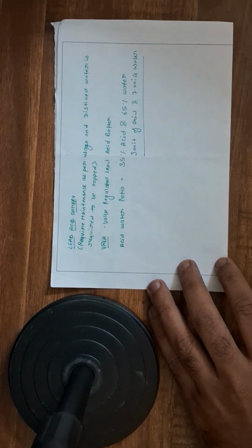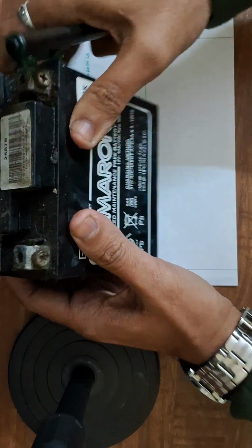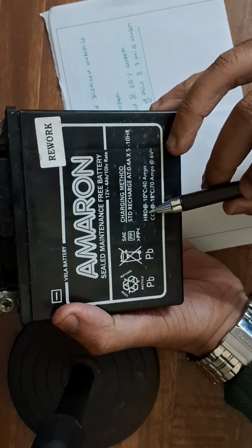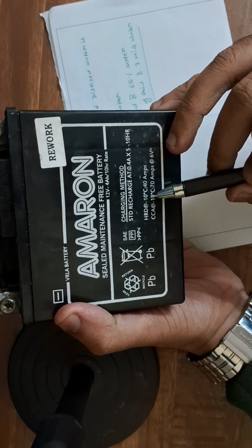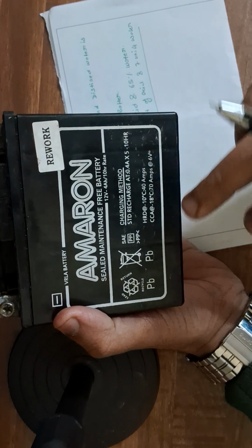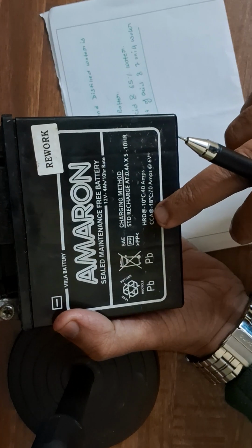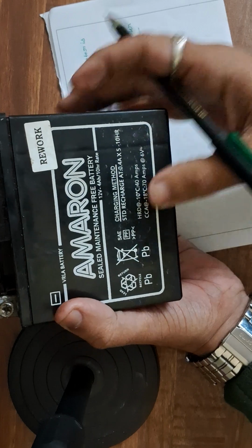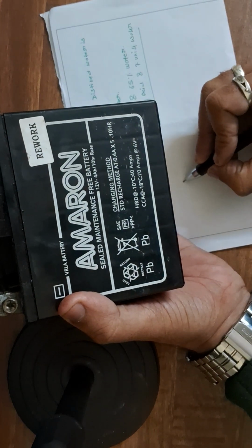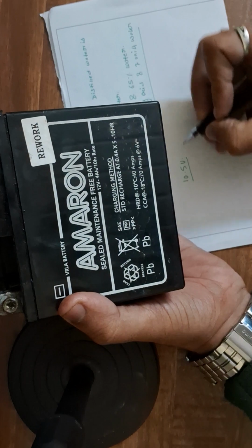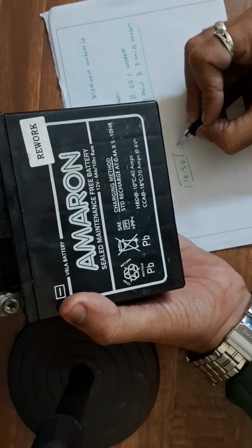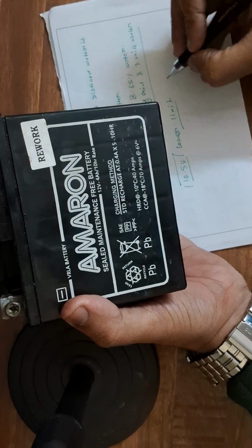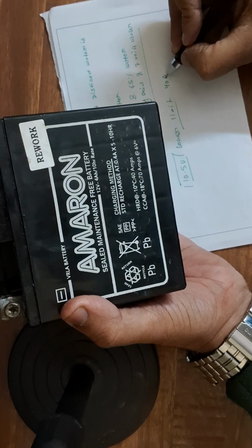Now what we were discussing, as I told you about an example: here it is written HRD, high rate discharge, at minus 10 degrees Celsius. All these tests are basically carried out at laboratory premises. When high rate discharge is performed, the voltage is specified to a lower limit of 10.5 volts, and discharged with 40 ampere current.